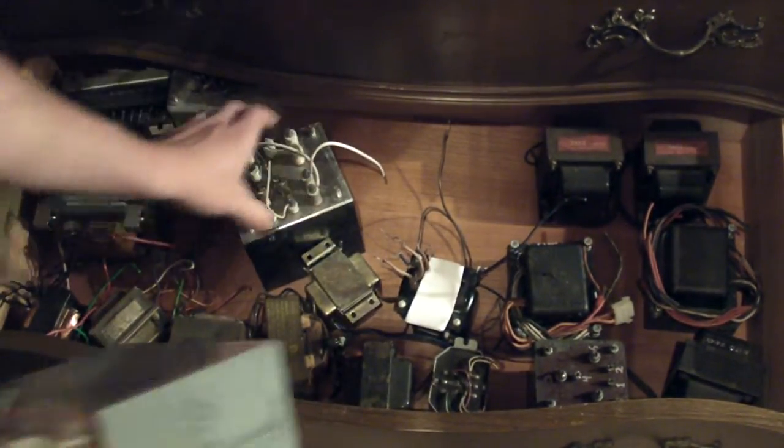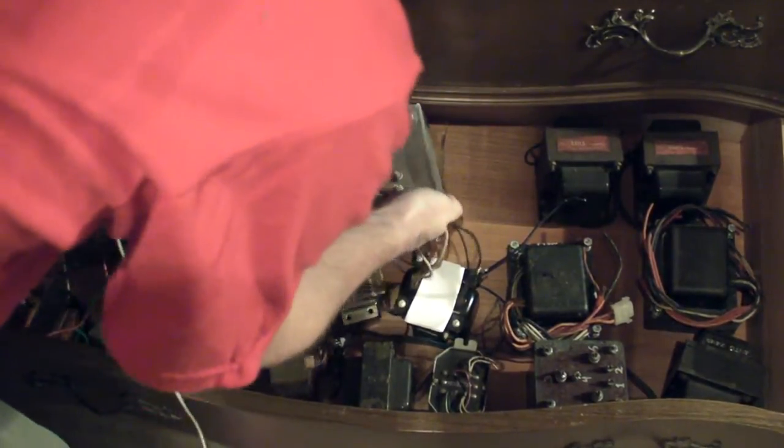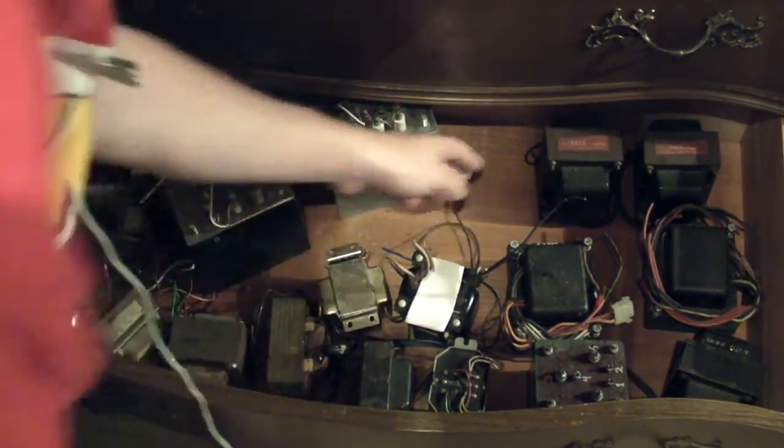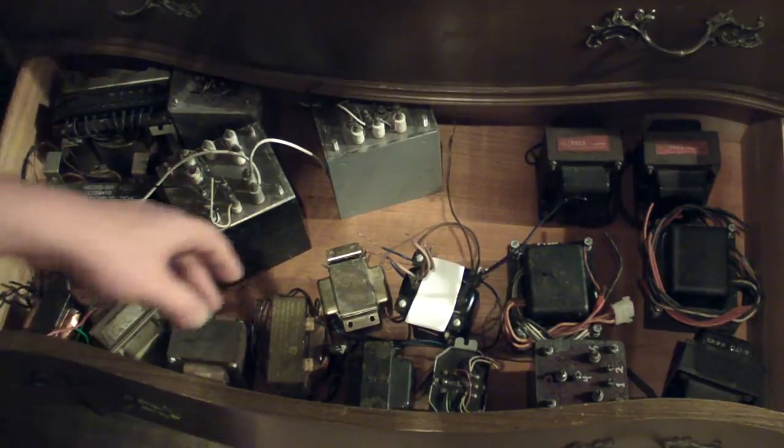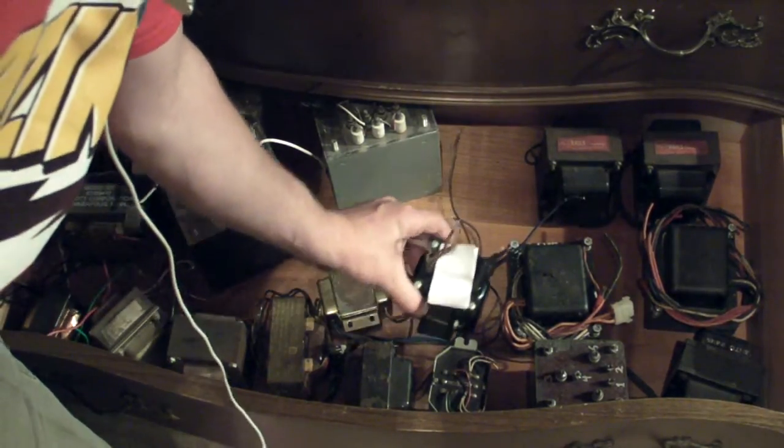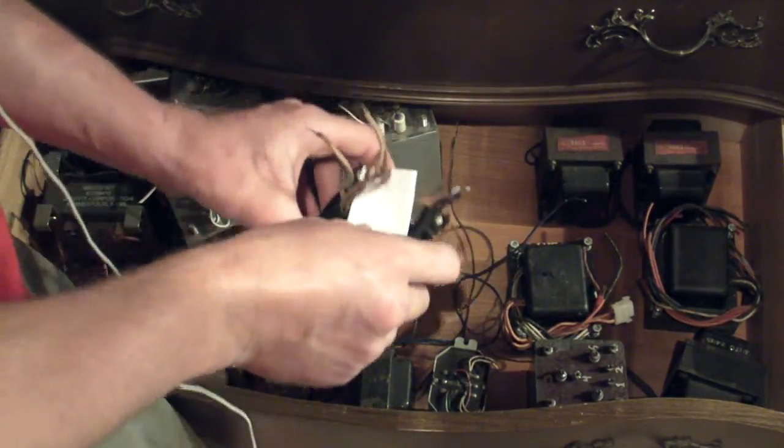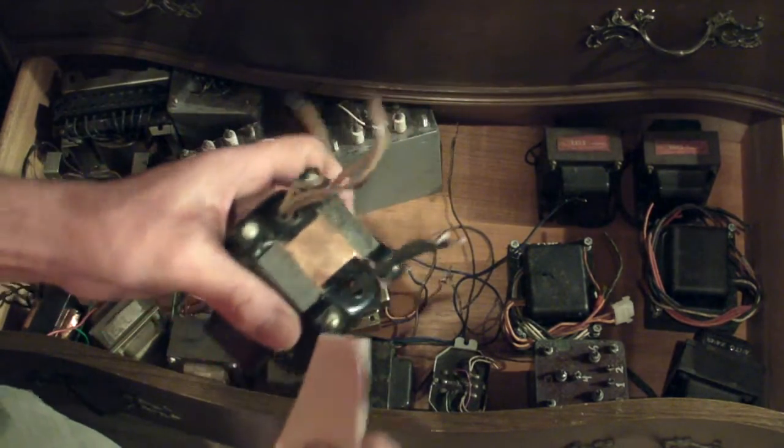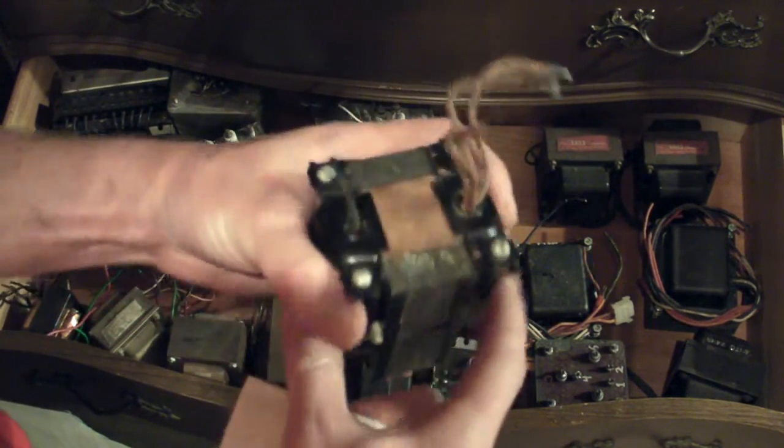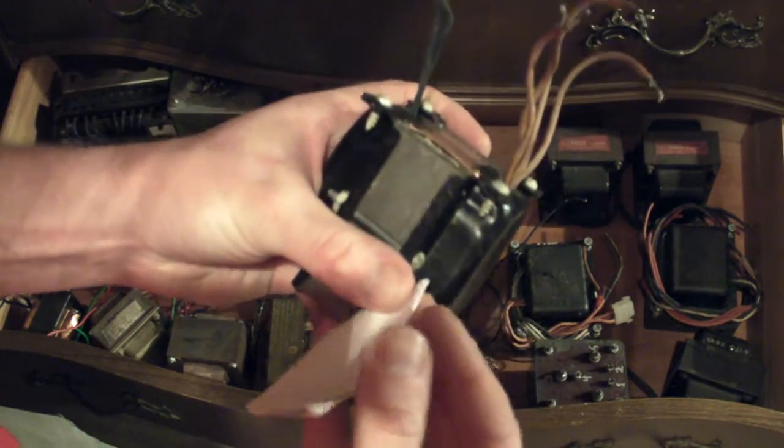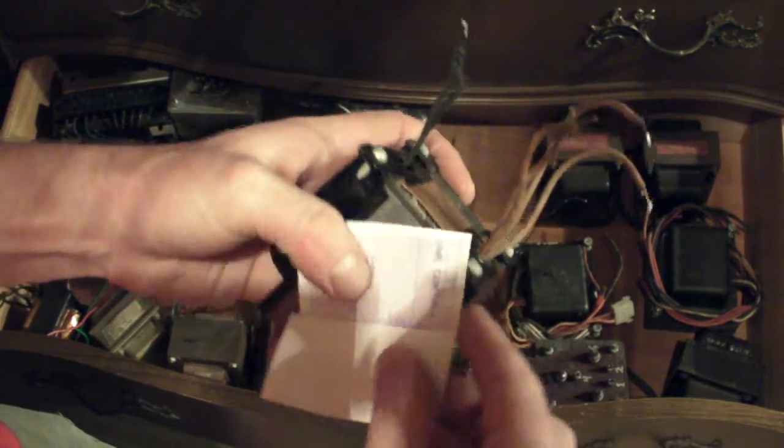I got another one right down here too, but the contacts are dirty. I don't feel like cleaning them because if I don't clean them I might get some arcing on the 2,400 volt output terminals.